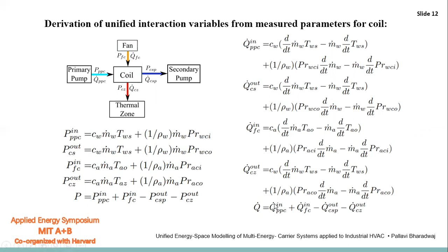Once we have these basic blocks characterized using the real and reactive power interface variables, we can decompose all the complex multi-energy equipment into these basic building blocks. For example, the fan and pump are analogous — they have the same energy space model with air or water as the respective energy carriers. Otherwise the equations remain the same; only the carrier changes. Similarly, the fan coil unit is basically built with fan and coil superimposed, so both models need to be combined to get the FCU model.